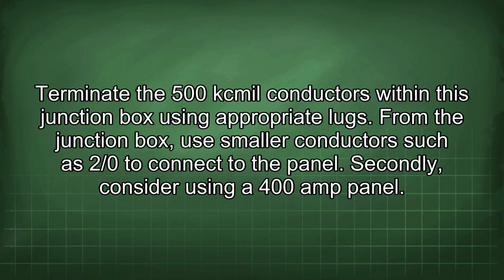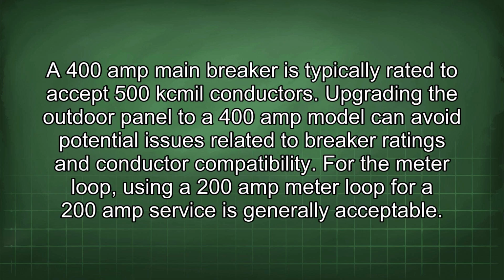Secondly, consider using a 400 amp panel. A 400 amp main breaker is typically rated to accept 500 kcmil conductors. Upgrading the outdoor panel to a 400 amp model can avoid potential issues related to breaker ratings and conductor compatibility.